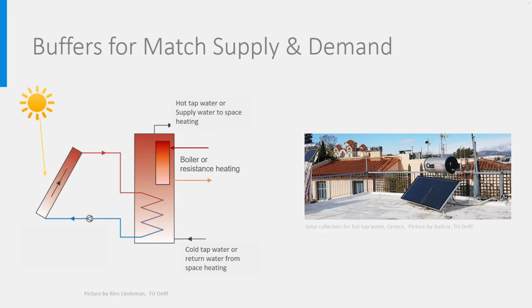When using solar thermal energy for hot tap water or space heating, we have to deal with the intermittency of solar radiation, and therefore a buffer tank is necessary. The tank is charged, heated, therefore, when the sun shines. In this type of buffer tank, there is a closed loop of water going from the solar collector to the tank. The tank itself is fed either by cold tap water or by the return water of the space heating. There is always an additional electric element or a gas boiler for additional heating of the tank when needed.